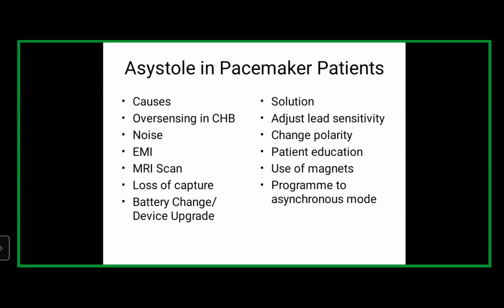So basically what you do then is program to asynchronous mode and step up the lower rate, or the base rate, so as to override whatever the baseline of the patient is.